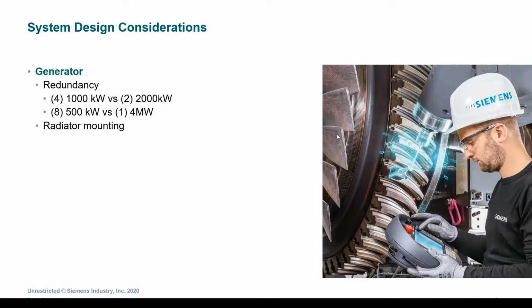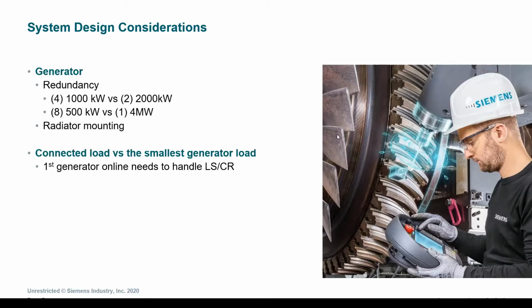should be evaluated. This would include the generator sizing compared to the redundancy. For example, there are multiple combinations of generators to get to a 4 megawatt capacity. Note that different sizes have different footprints and potentially separately mounted radiators, impacting the layout and the configuration. Conversely, it's important to size the generators, where possible, in a manner that the generators can carry all of the emergency Article 700 loads. We'll dive into this more in detail in a few minutes.